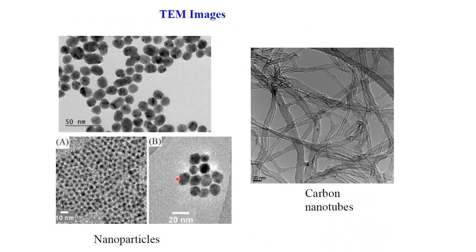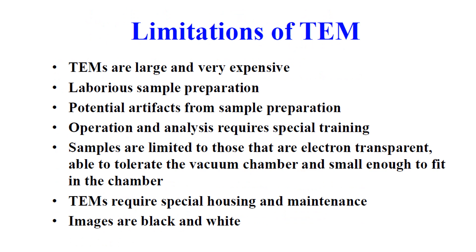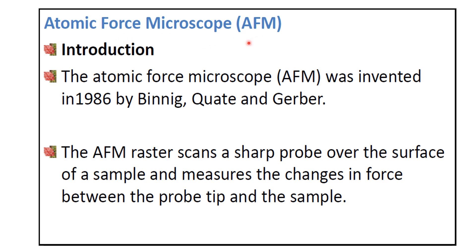These are TEM images of different nanoparticles and carbon nanotubes or fibers. TEM can be used in biology, microbiology, nanotechnology, and forensic sciences. It can study bacteria, viruses, nanoparticles, and nanopowders, and can also detect defects in various specimens or devices. Limitations include that TEMs are very large and expensive, sample preparation is very laborious, high vacuum is needed, and special housing and maintenance are required. Images are black and white.